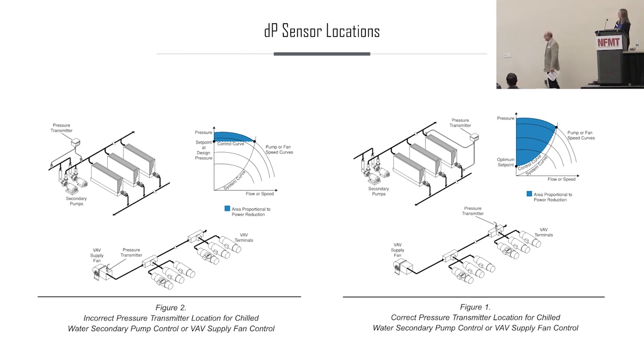Now, one of the starting points we did want to talk about, because we see this one fairly often, is where are things like the pressure differential sensed at? Inevitably, a lot of times during construction, because it's the lowest cost method and the easiest thing, and the controls contractor wants to get in and get out at the lowest possible cost, they'll put the DP sensor there in the mechanical room, just supply, return, boom, let's go.